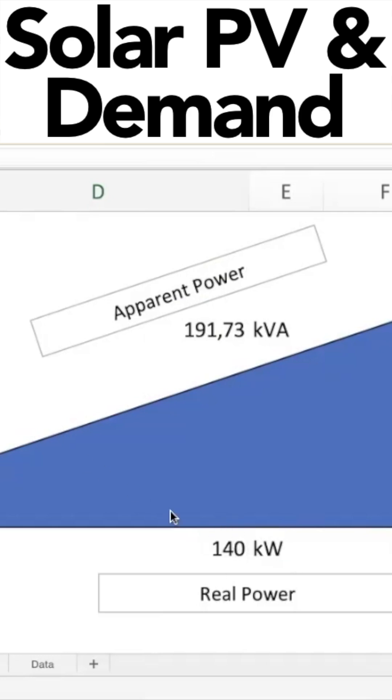So let's assume that it's a weekend and you are drawing 140 kilowatts. Your system shows a demand of 190 KVA. I'm going to change the kilowatts at the bottom over here. So let's assume you've got 120 kilowatts being provided by the solar system. So you're only drawing 20 kilowatts from the grid.